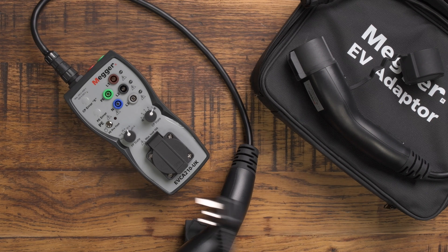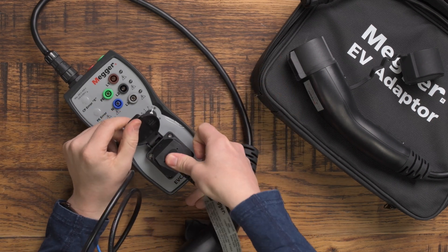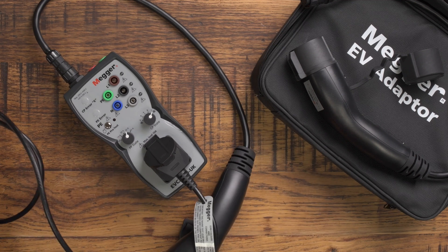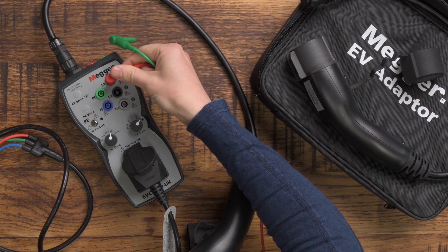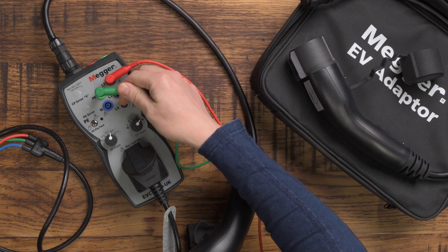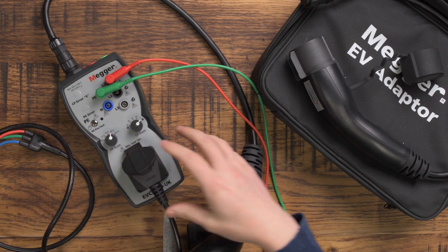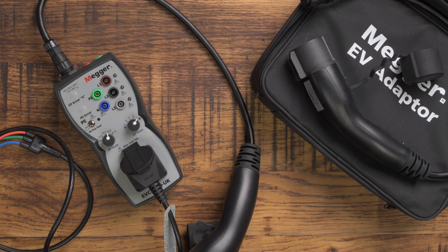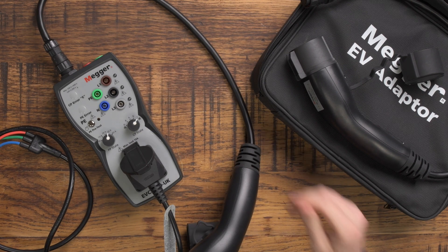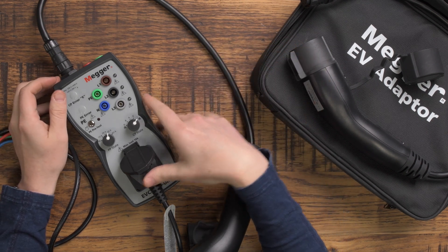So for example if I've got my Megger tester here, I can plug my tester in there, or if I prefer I can plug my test leads in here like this. Then I'll have voltage at my tester and I can do the various tests I need to do, such as earth loop impedance, RCD test, check the voltage, and all that stuff.